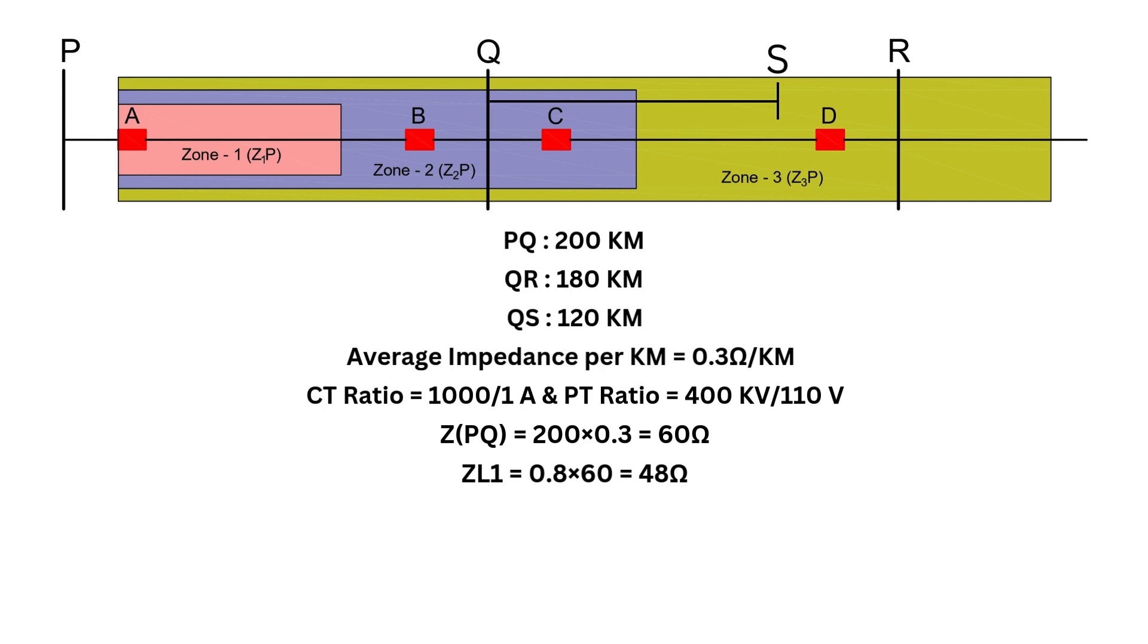But wait, we need to consider the CT and PT ratios because the relay measures voltage and current through them. Let's find the combined CT-PT ratio, which is 0.28. Now we apply this ratio to the impedance. 48 × 0.28, which equals 13.44 ohms.